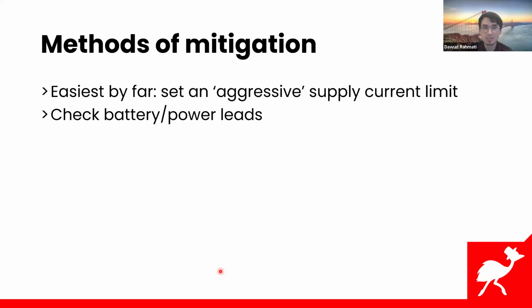You need to check your battery and power leads and make sure they're actually solid. Many times I've seen either the battery leads that connect directly to the battery, your circuit breaker leads, or anything in between, if they're loose, that's going to add resistance into your power path. And we don't want more resistance, we want less. So if it's loose, it's a worse connection, and electricity is not going to flow as well.